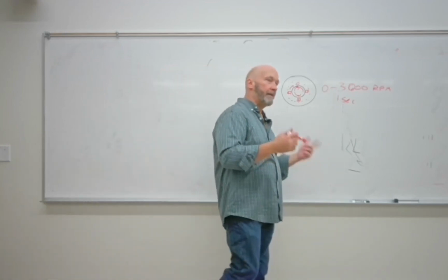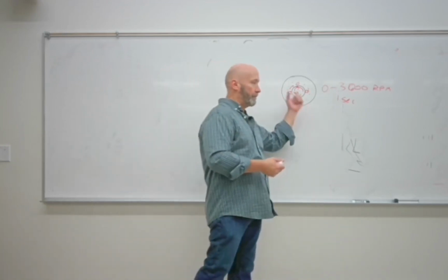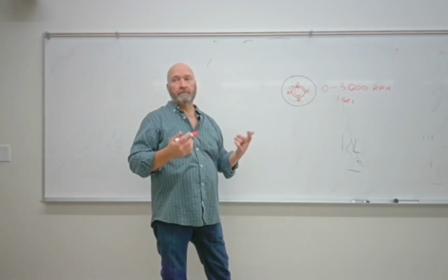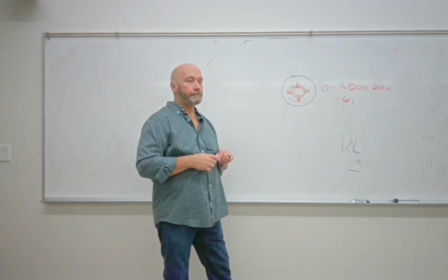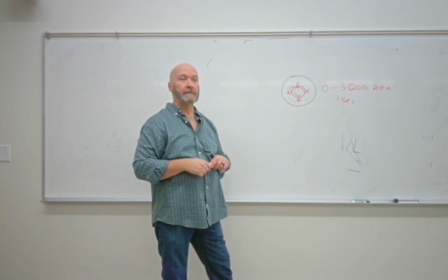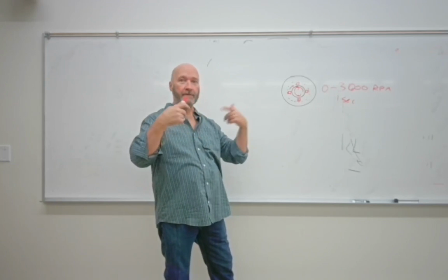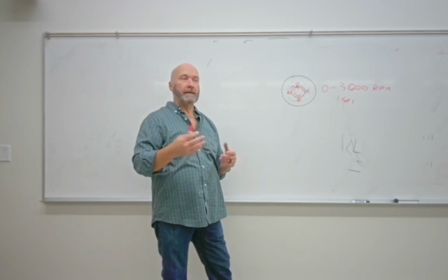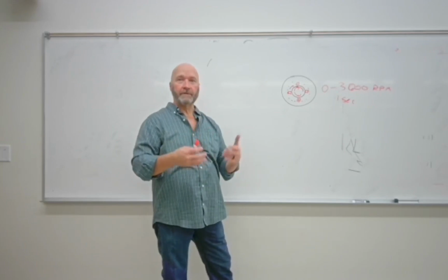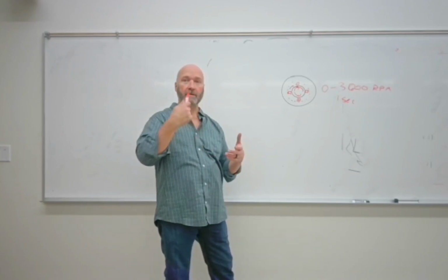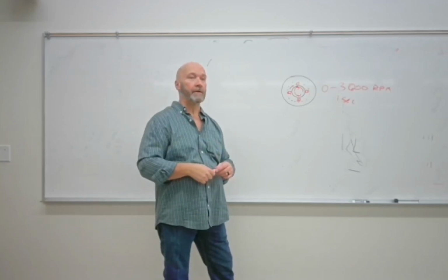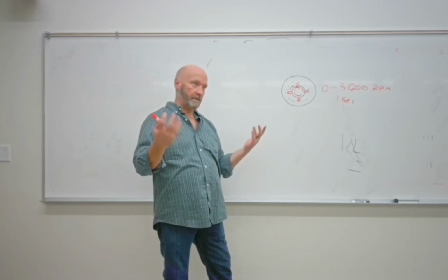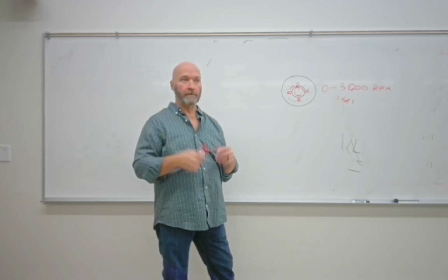What happens is after you make your exposure, the electromagnets fire in a reverse sequence to stop your rotor. Now, why would we want to do that? Wear it down, exactly. They have to turn on something. We'll get into this a little bit later on, but the longer it turns, the more it wears out the bearings, and the quicker the life of your X-ray tube is going to be over.